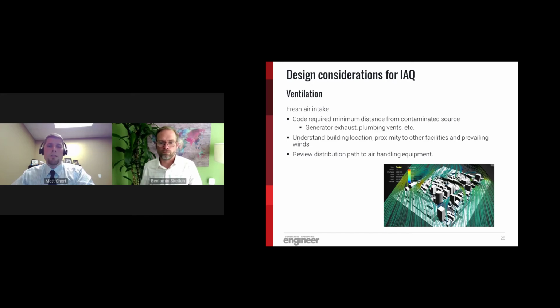It's also important to consider the path of fresh air from the exterior of the building to the location of your outside air intake. What I mean by this is consider how neighboring facilities, obstructions, and prevailing winds might have an impact on the quality of fresh air that we provide to the building. The image below indicates a prevailing wind study, which shows potential pathway obstruction for a building's outside air intake.